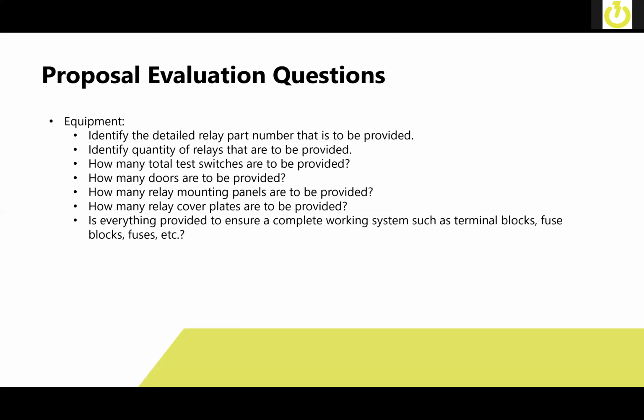The quantity of relays that are provided, how many test switches are to be provided, how many doors or relay mounting panels are to be provided. For instance, do you want the door to be completely replaced, or do you just want a relay mounting plate that covers up the old equipment and is mounted to the existing door? How many relay cover plates? For instance, you may have equipment located throughout the facility that you want to take off and demolish that's no longer being used. Do you want to take that relay out and put a cover plate on it, or do you just want it to be flagged as out of service? There are advantages and disadvantages to both of those options.